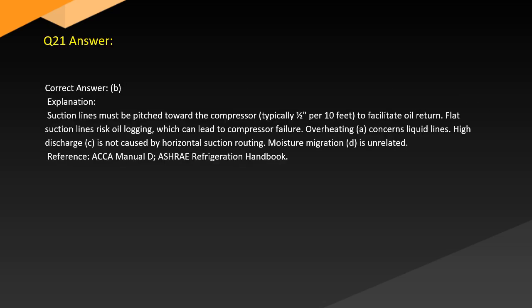Answer. Correct answer: B. Explanation. Suction lines must be pitched toward the compressor, typically 1/2 inch per 10 feet, to facilitate oil return. Flat suction lines risk oil logging, which can lead to compressor failure. Overheating (A) concerns liquid lines. High discharge pressure (C) is not caused by horizontal suction routing. Moisture migration (D) is unrelated. Reference: ASHRAE Refrigeration Handbook.